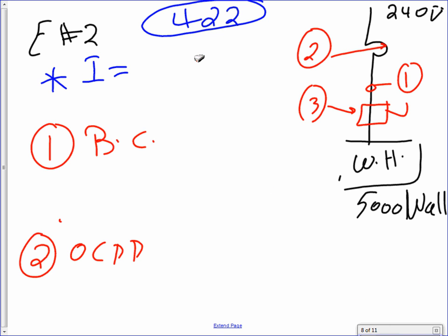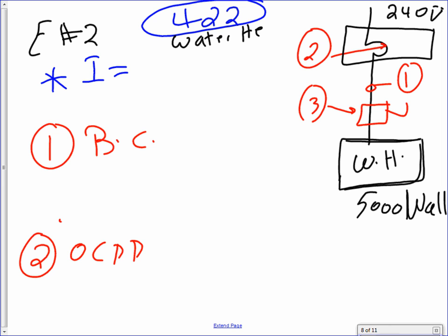Can you guys draw this thing for me, please? Take a few seconds to draw. I'll give you a few seconds here. This is a water heater. And my system, my panel is 240, 120. And I need to size the fuse or the circuit breaker, the conductors, as well as the disconnect for this water heater. So again, this example is for a water heater.